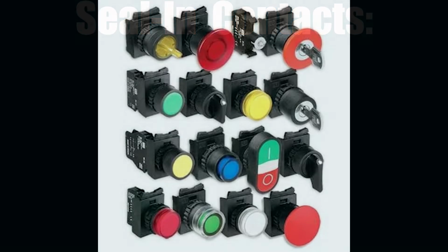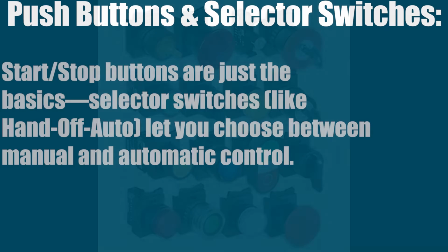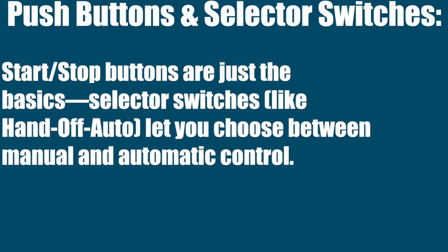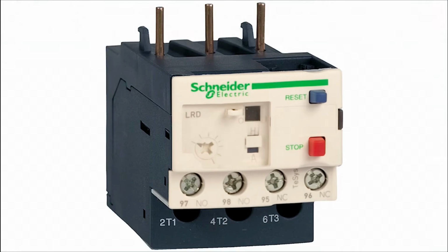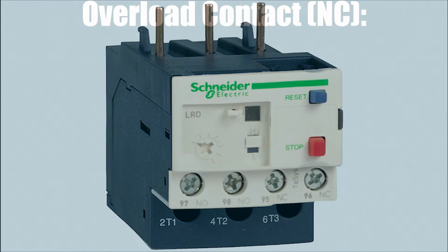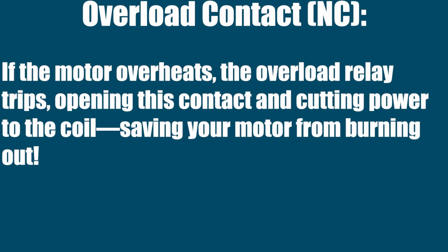So push buttons and selector switches, start, stop buttons, these are just the basics. Selector switches like hand, off, auto, these let you choose between manual and automatic control. Overload contact, that's normally closed in series with the coil. If the motor overheats, the overload relay trips. This opens the contact and cuts the power to the coil, saving your motor from burning out.